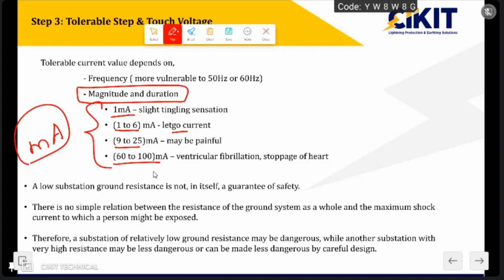So the parameters on which the damage depends are frequency, magnitude and duration of the fault currents. And one of the important points that we have to note when we are working with IEEE 80 is that IEEE 80 is one of the standards which highlight that earth electrode resistance value does not have direct impact on the safety. They have clearly mentioned that a low substation ground resistance itself is not a guarantee of safety.